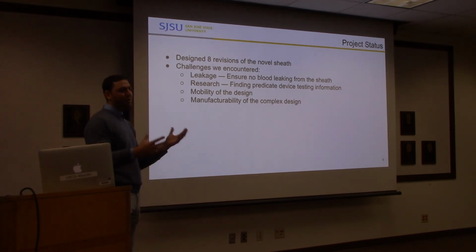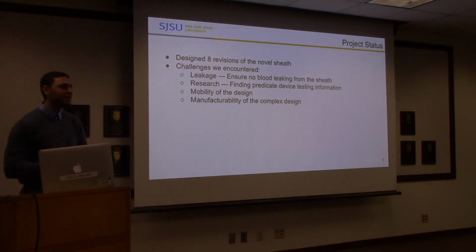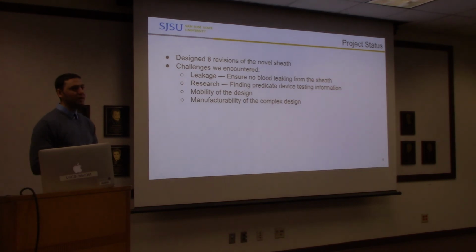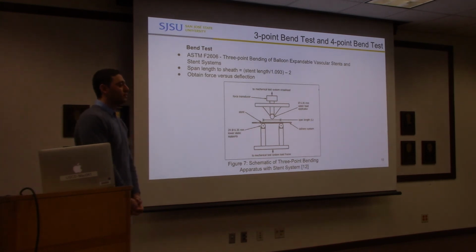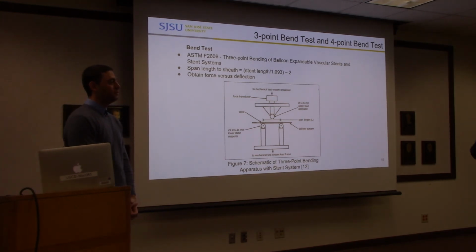Yeah, so we went through complex design, then we went through assembly design to ensure that it not only does the job, but is also manufacturable. So with that, we went ahead and bought some predicate devices. We want to do the 3-point bend test and the 4-point bend test. This is one of the ASTM standards that we based it off of.